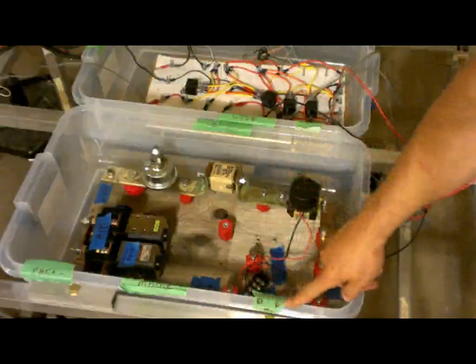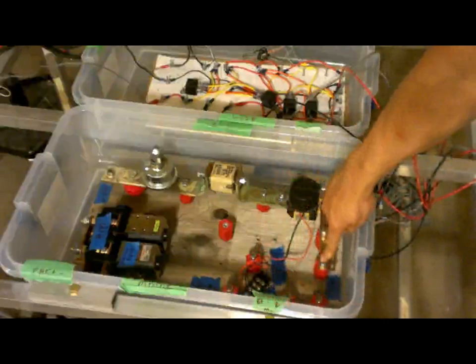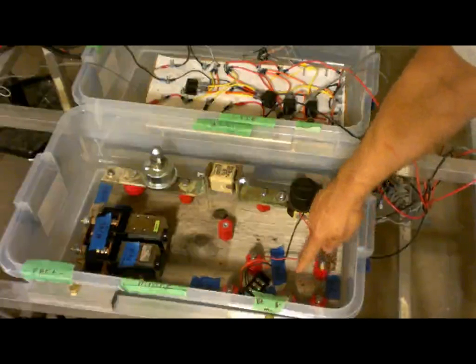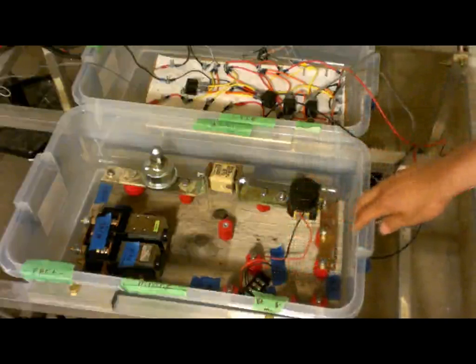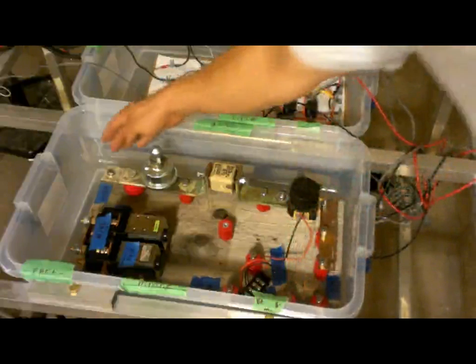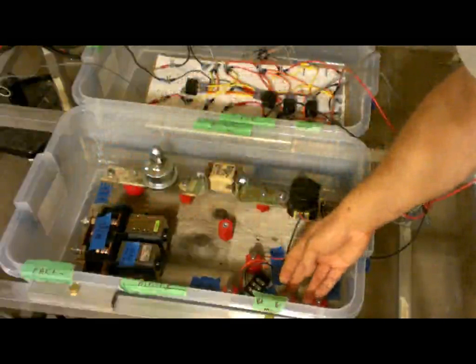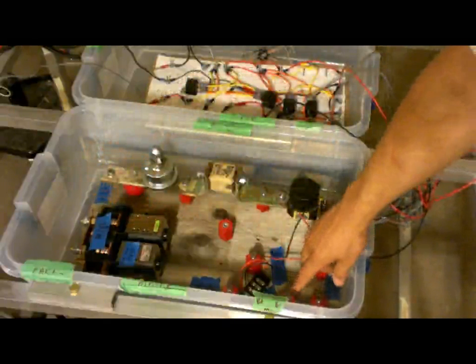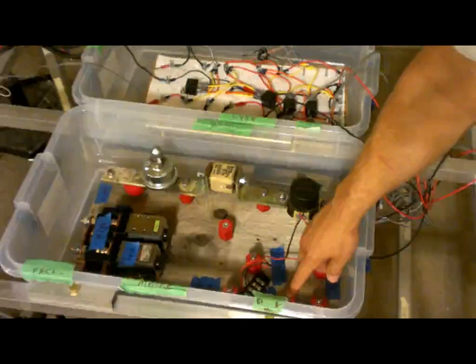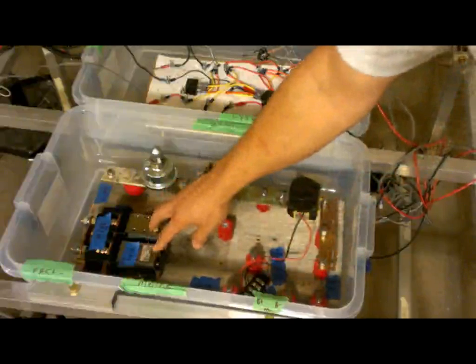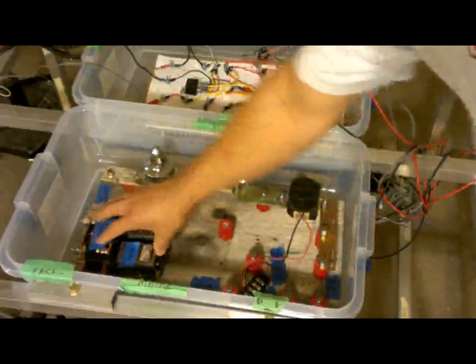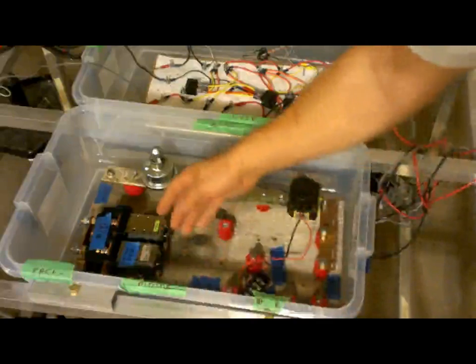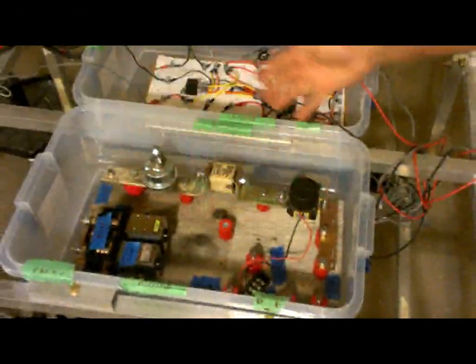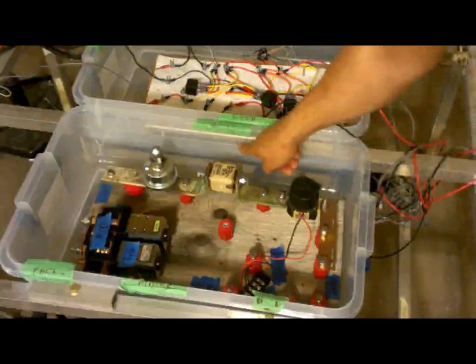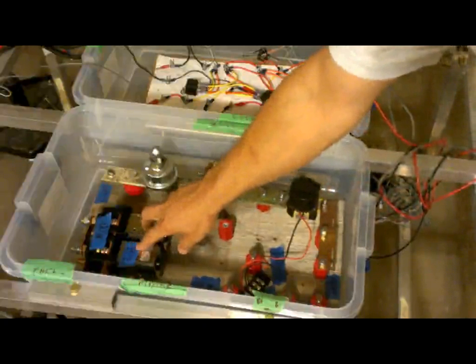The controller is going to be coming into this side. We've got three connections: one for B+, one for B-, and one for M-. So those are going to be kind of clustered over here. The negative on the pack is going to be going up to the negative on the controller. Then we've got the negative on the controller going to the reversing contactor. There's 4 cables that come off the reversing contactor that are going to go to the motor right down here. And then the pack cable is probably going to come in from this side. That's the cables coming in and out of the high voltage junction box, except for the signals for the contactor and for the reversing contactor.